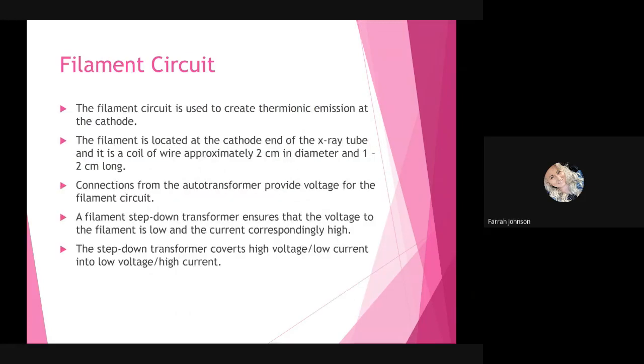Then you have your filament circuit. Now, the filament circuit is what's used to create thermionic emission at the cathode for X-ray production. The filament is located at the cathode end of the X-ray tube, and it is a coil of wire approximately 2 centimeters in diameter and 1 to 2 centimeters long. Now, note that your filament is going to heat up and boil off electrons that are going to travel across the X-ray tube to your anode. Okay, so that is what the thermionic emission portion is.